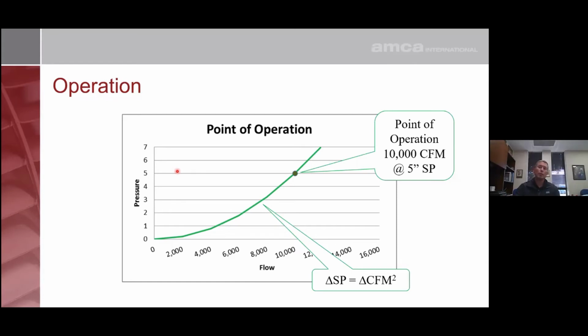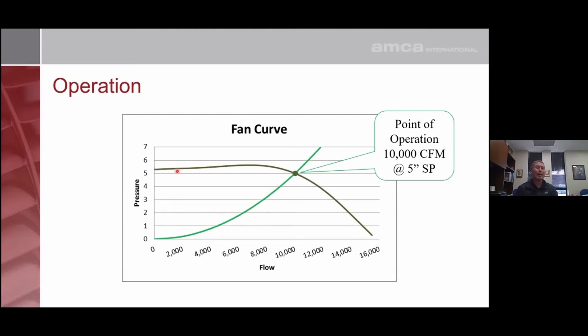So where the fan's going to operate is the intersection between that system curve and our fan curve, and that point only. It cannot operate at any other point unless you physically change something in the system. So for example, if you have a damper and you close it, that's going to shift this whole curve to the left. If you have branches that are closed off and you want to open up some of the branches, that'll shift this whole system curve to the right.